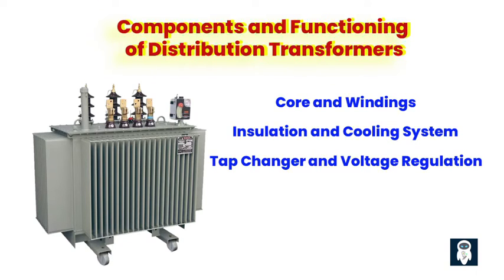To prevent any unwanted sparks or short circuits, distribution transformers are equipped with insulation materials that create a barrier between the windings and the core. This insulation is crucial for maintaining the safety and efficiency of the transformer. Additionally, distribution transformers have cooling systems such as fans or oil-filled radiators to prevent overheating. Distribution transformers also come with a tap changer, which allows for adjustments in the turns ratio of the transformer, thereby regulating the voltage output. When there are fluctuations in the incoming voltage, the tap changer ensures that the voltage reaching our devices remains stable and safe.